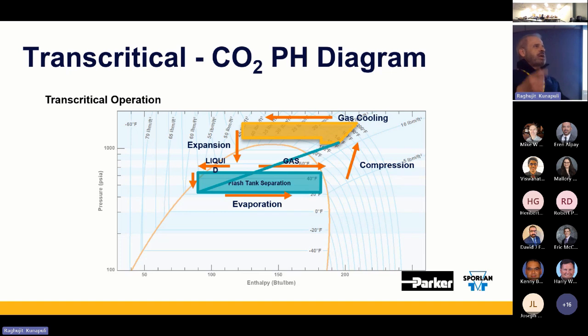They had some that had some false load on them and they were showing off what they could do. But transcritical CO2 systems, I was told, you would only see in environments where you wouldn't have excursions above 88 degrees Fahrenheit, or at least not very often, because that holds with it a whole host of fancy engineering gymnastics that you've got to pull off.